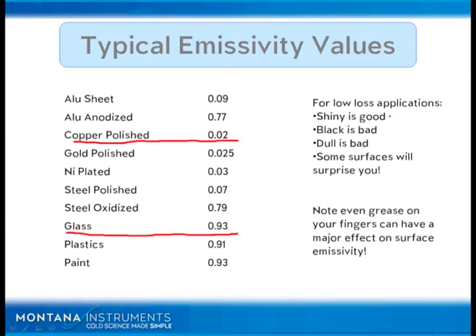So you can take a very nice surface, and if you're always handling your cryogenic parts with your bare fingers, you will have a buildup of oils on every one of those parts and your emissivity goes up, and in the end your heat loads in the cryo will go up. On top of that, the finger oils will also fly away when you pull vacuum and they'll end up on some cold surface.